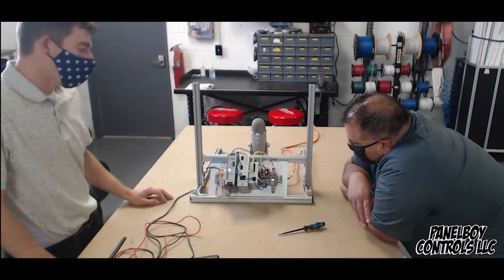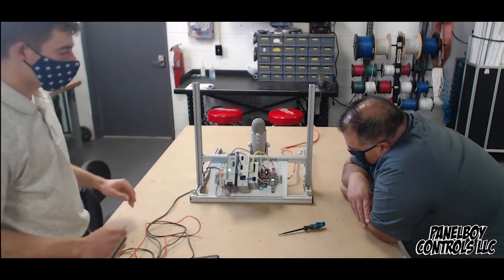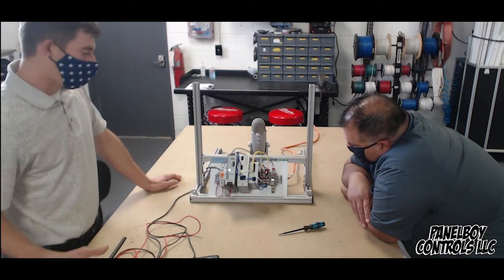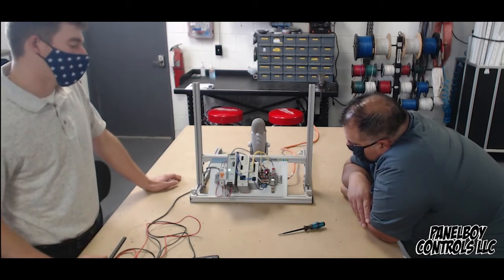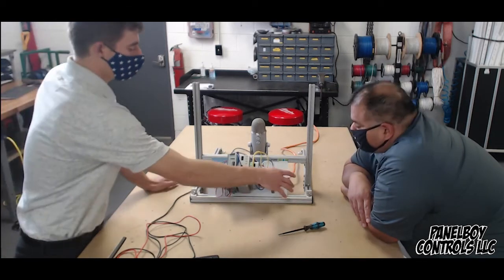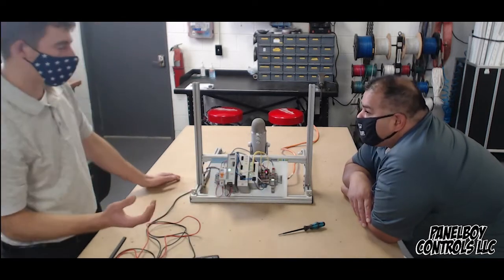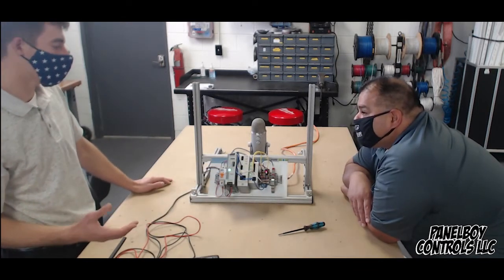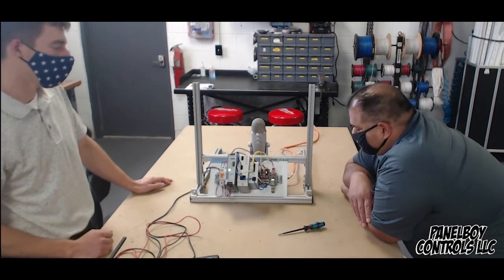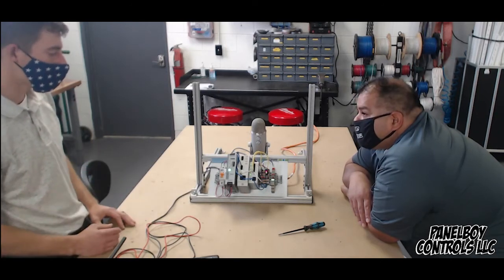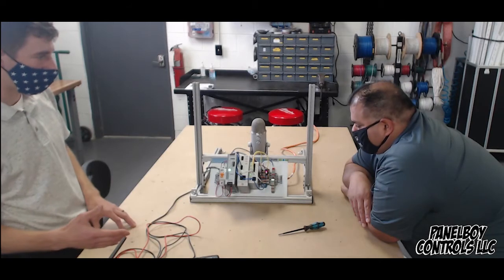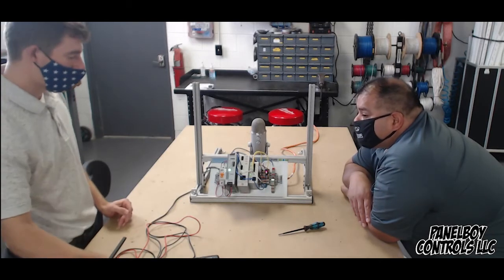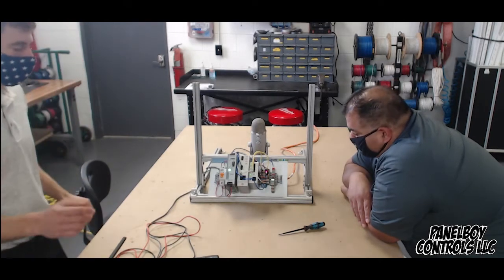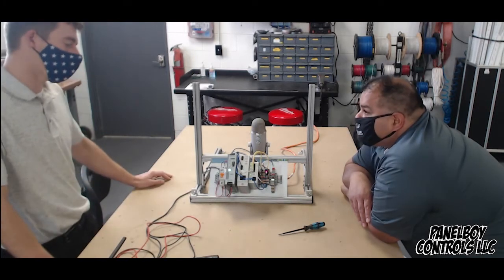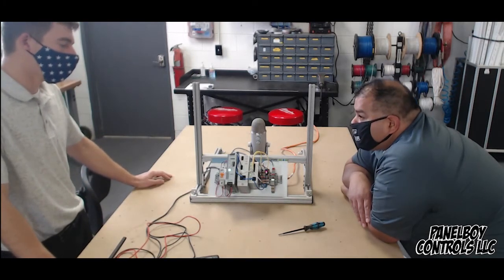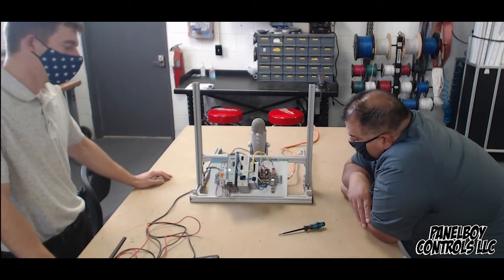And the real advantage is there. Maybe you've got a whole bunch of different devices there, and it's working fine, but one day you have a problem and it trips. That means that something on that bank of terminal blocks that's restricted to 4 amps is going bad. You typically know what the nominal voltage of your system is. So once it creeps past that, there's something, maybe an Ethernet switch, a drive, or a field device that's connected and powered by that. That's where you get the important information from. That's pretty cool. I like that.